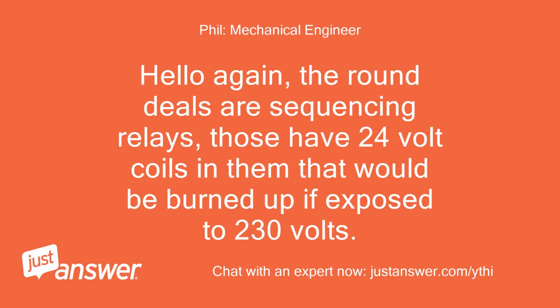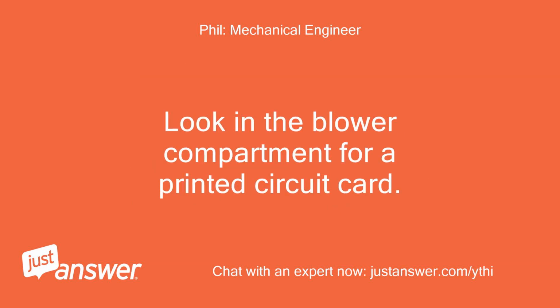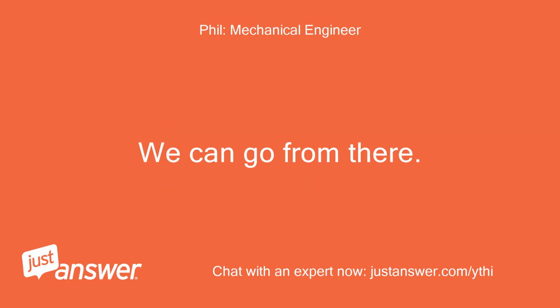Hello again. The round deals are sequencing relays. Those have 24-volt coils in them that would be burned up if exposed to 230 volts. Look in the blower compartment for a printed circuit card. We can go from there.